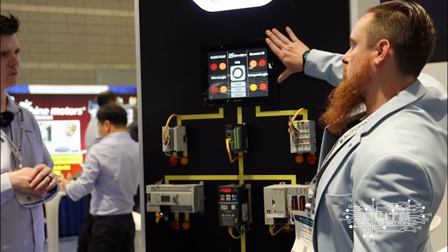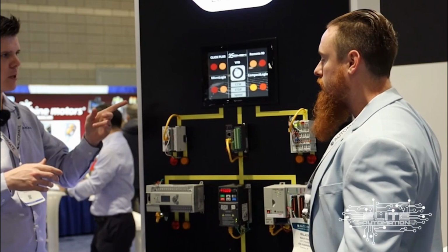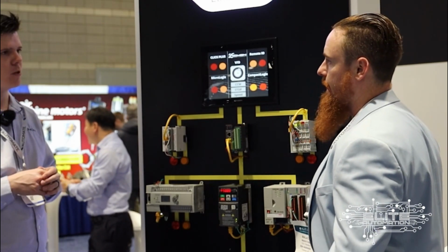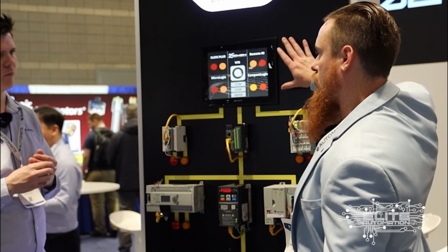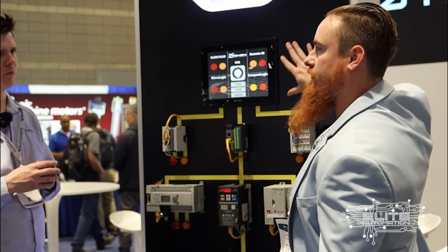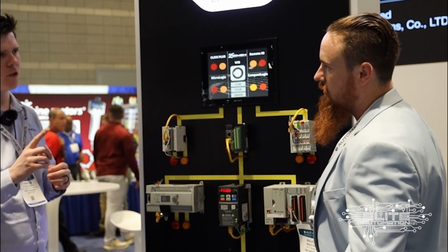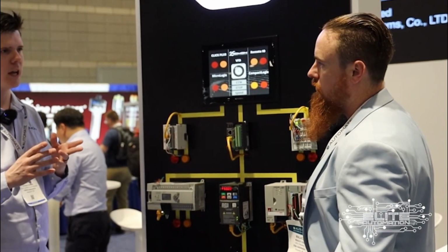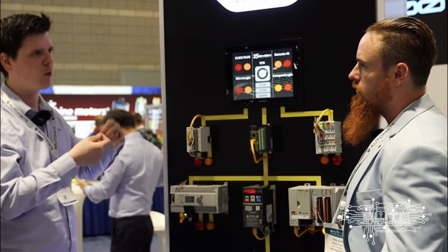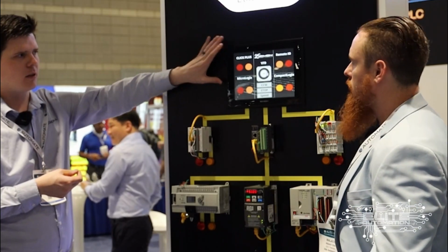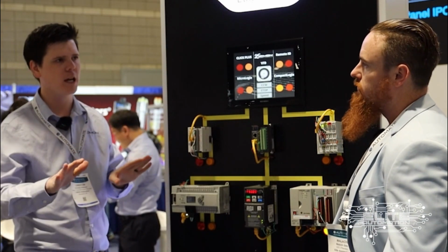Now, does this HMI also have cloud capabilities, or is it a different model? It has OPC UA server and client, and has MQTT. Okay, so those are your cloud-based protocols right there. And do all your HMIs support it, or are there certain variants? All of them. Now the 4-inch HMI only has one Ethernet port, so you might not find a good use case. You could connect over serial to your field devices and then use the Ethernet port for the cloud. But what makes this smoother is you have 2 Ethernet ports. Gotcha. But the 4-inch, you still could do it, there's no limitation on the size.